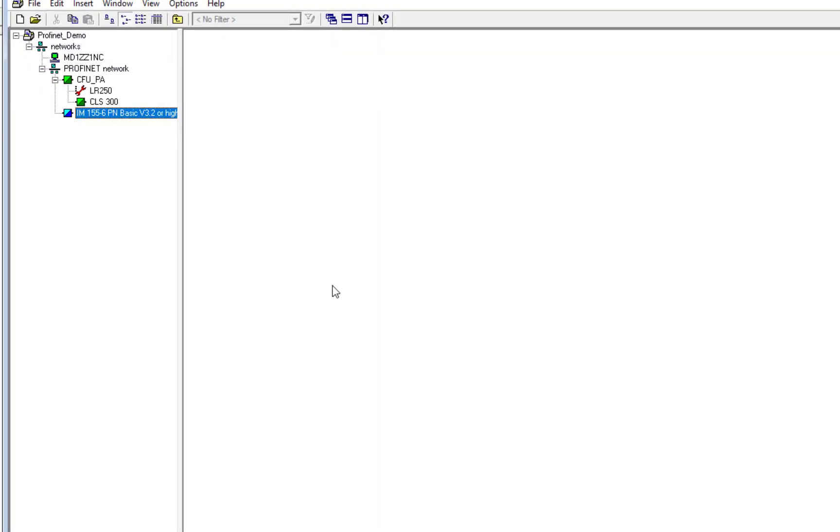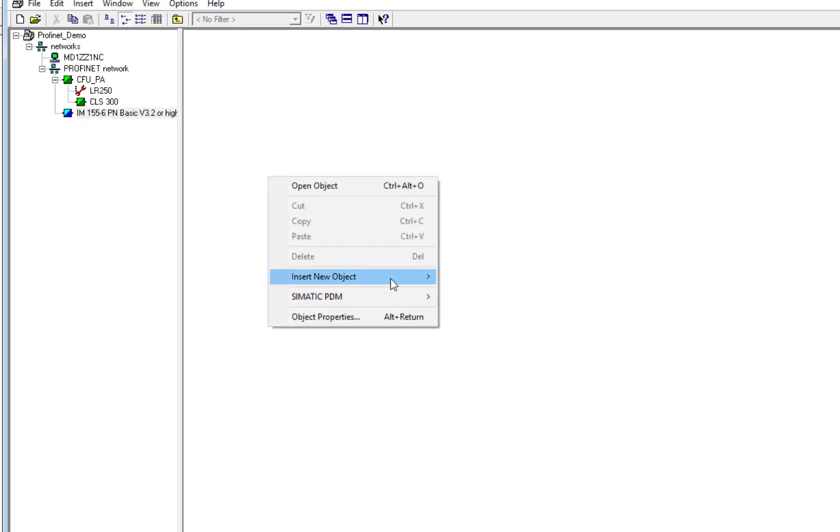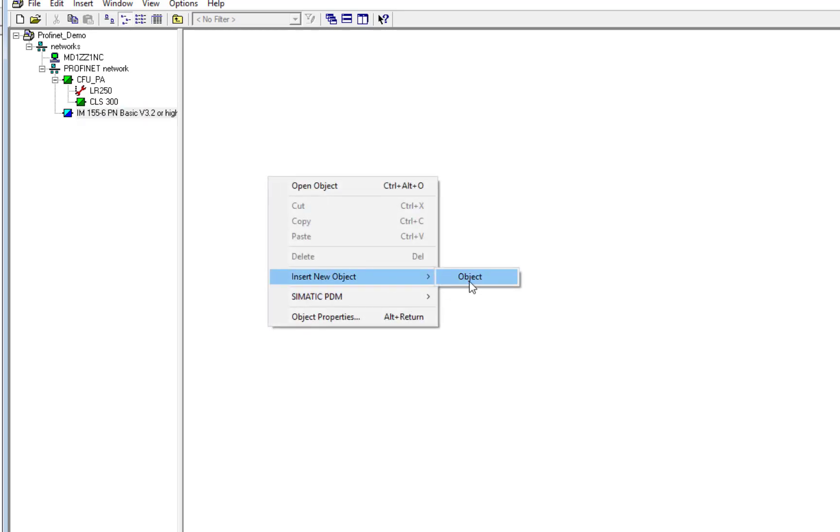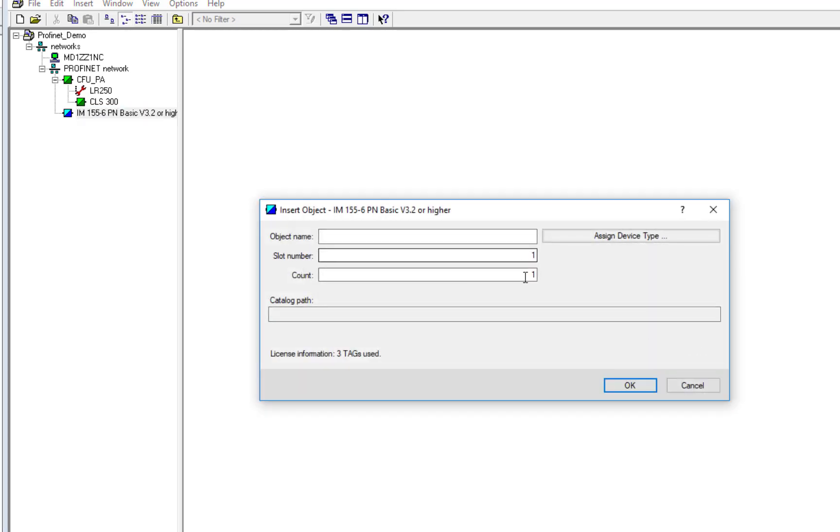Underneath here, we're going to have various IO cards in different slots. So on this particular project, in slot 1 or slot 0, I have a weighing card, and then in my next slot, I have a HART input card. So under the IM, if I click Insert New Object, you will see here slot number. So that's the very first slot number. I'm not too sure if that differs from how the PLC refers to it as slot 0, but PDM, the first slot, is always slot 1.